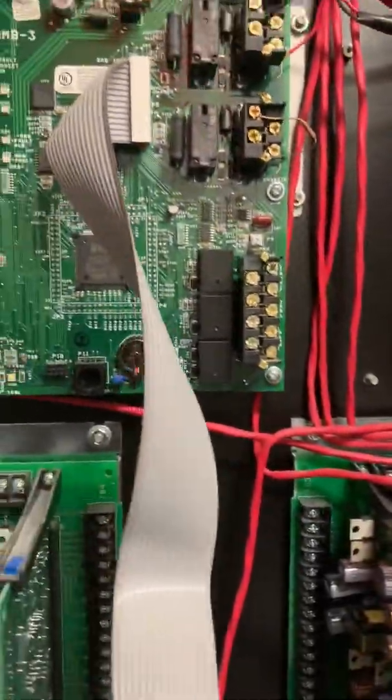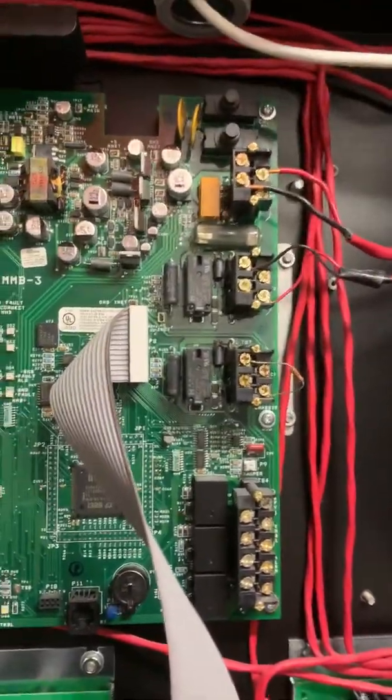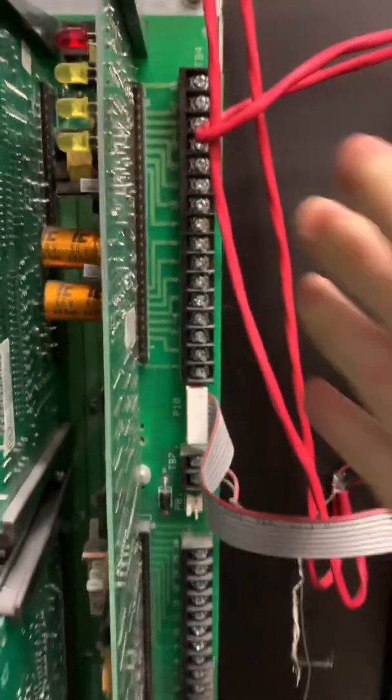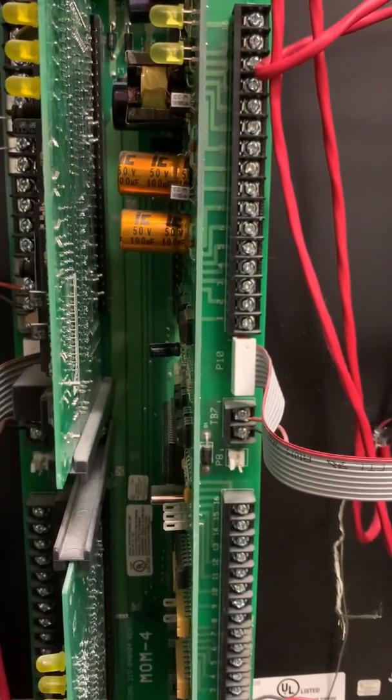Opening up the panel we have the MMB3 — this is basically the main board. You can see a ribbon cable right here, our 120VAC power supply coming in here, and then the main board going down. We have more XL3 cards here as well. We also have an ALD card, where some of the newer MXL devices communicate, and all of it goes back to these MOM boards. These are all the cards that are supervising and constantly talking to the devices out in the field.